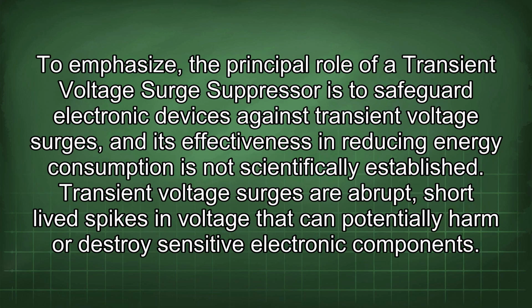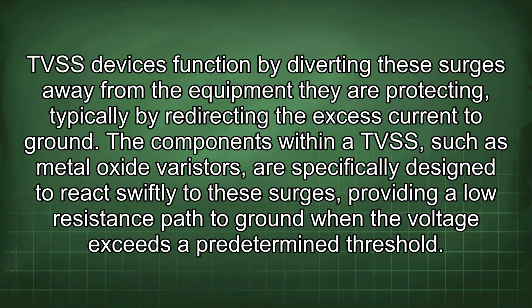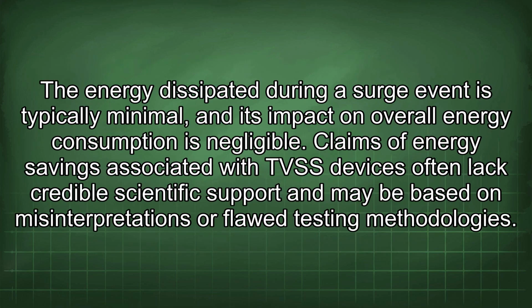To emphasize, the principal role of a transient voltage surge suppressor is to safeguard electronic devices against transient voltage surges, and its effectiveness in reducing energy consumption is not scientifically established. Transient voltage surges are abrupt, short-lived spikes in voltage that can potentially harm or destroy sensitive electronic components. TVSS devices function by diverting these surges away from the equipment they are protecting, typically by redirecting the excess current to ground. The components within a TVSS, such as metal oxide varistors, are specifically designed to react swiftly to these surges, providing a low resistance path to ground when the voltage exceeds a predetermined threshold. The energy dissipated during a surge event is typically minimal, and its impact on overall energy consumption is negligible.